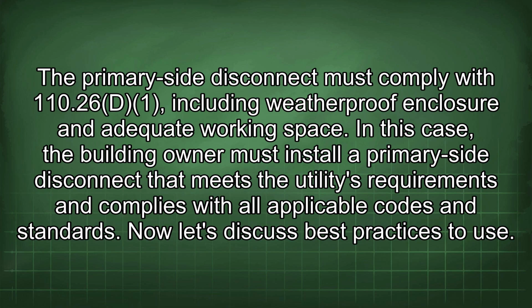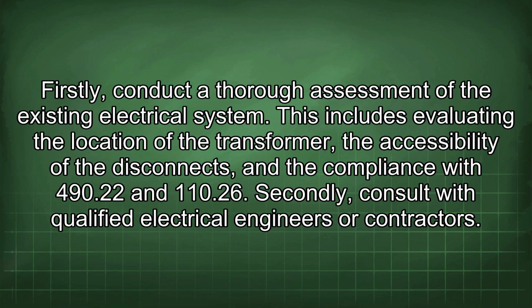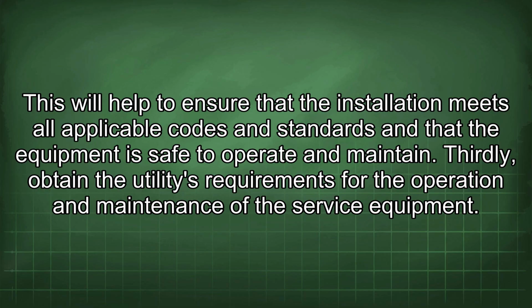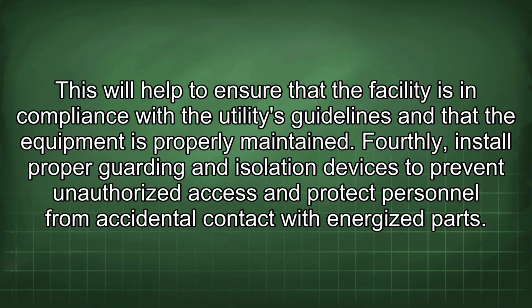Now let's discuss best practices. Firstly, conduct a thorough assessment of the existing electrical system. This includes evaluating the location of the transformer, the accessibility of the disconnects, and the compliance with 490.22 and 110.26. Secondly, consult with qualified electrical engineers or contractors. This will help to ensure that the installation meets all applicable codes and standards and that the equipment is safe to operate and maintain. Thirdly, obtain the utility's requirements for the operation and maintenance of the service equipment. This will help to ensure that the facility is in compliance with the utility's guidelines and that the equipment is properly maintained.